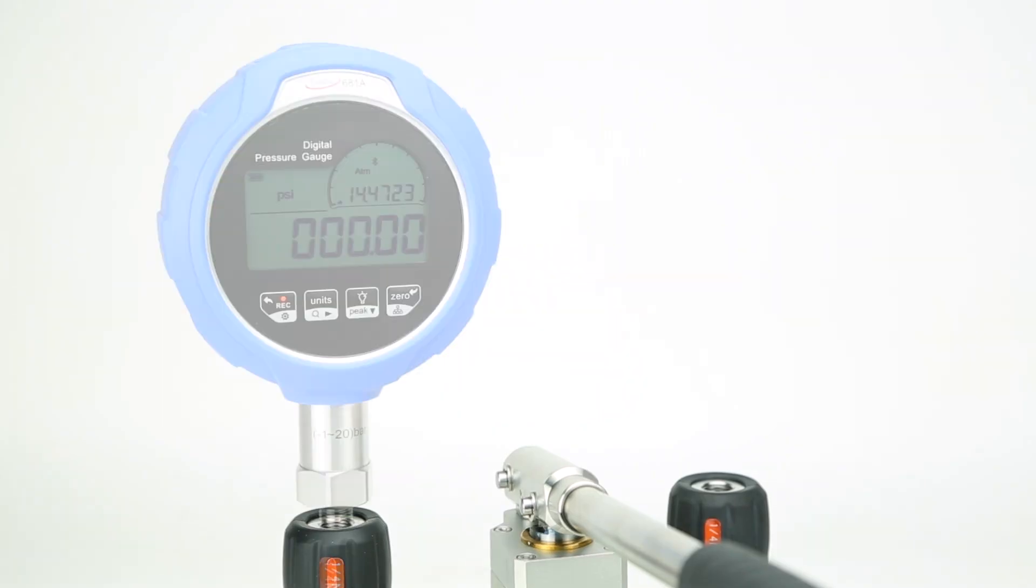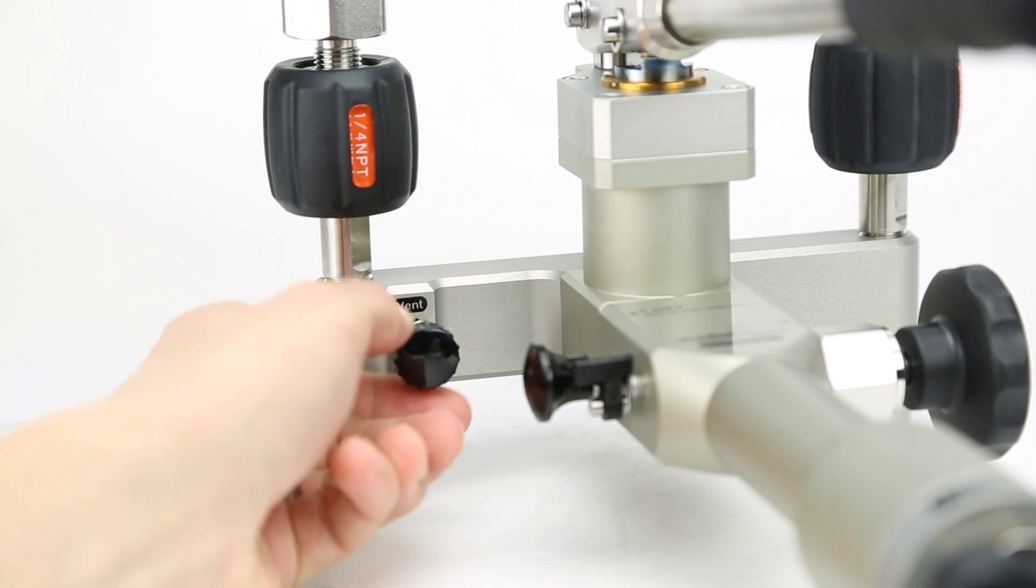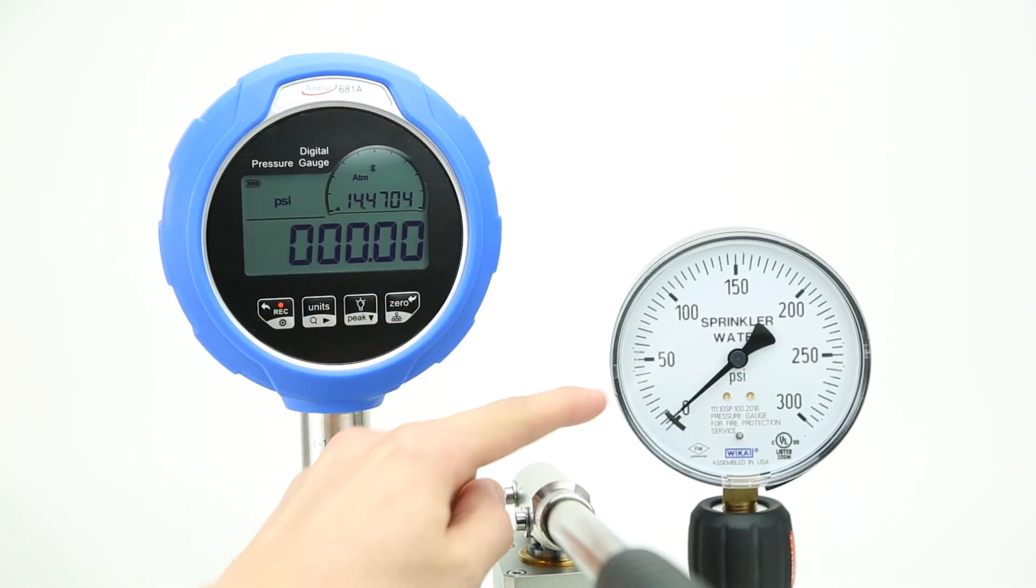To begin, connect both the reference and the DUT to the pump, and vent any pressure built up inside. While the pump is vented, you can zero the reference gauge and record the dial gauge pressure as your first calibration point.